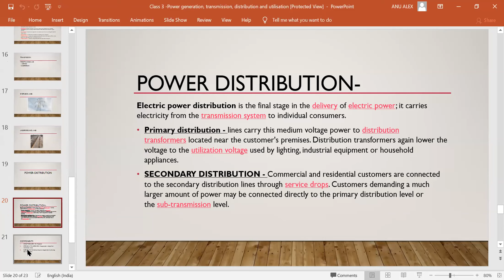The primary distribution, mostly you will not be able to see where it is happening, but that is another stage - the first stage at which the voltage is stepped down to a lower value, maybe to 66 kV, or maybe directly to 11 kV. This depends on the power structure or power network being utilized.